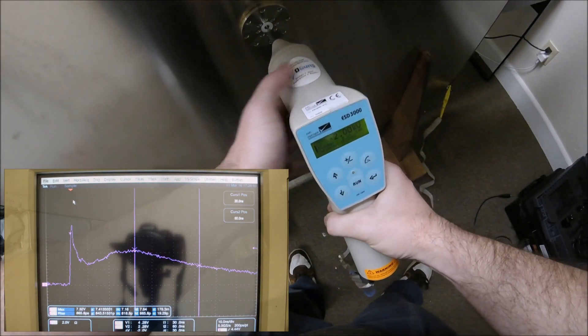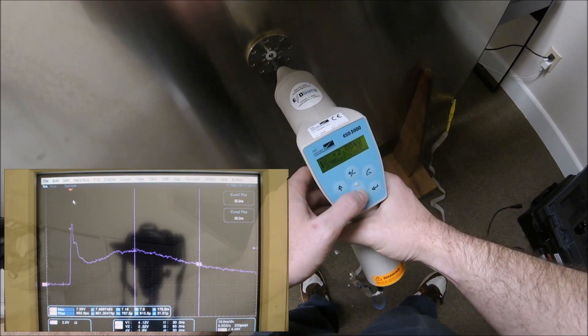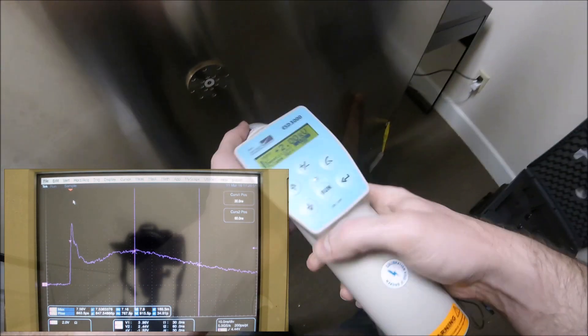In my hand is the EMC Partner ESD3000. We just increased the speed to 10 Hz. These higher speeds are used to identify susceptible points in a device.